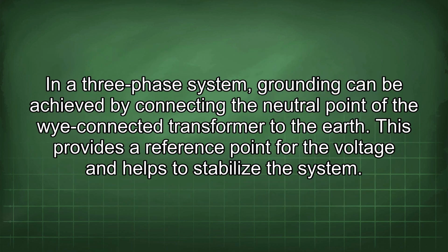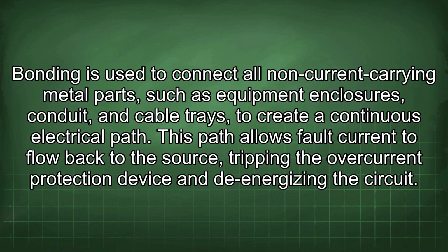In a three-phase system, grounding can be achieved by connecting the neutral point of the Y-connected transformer to the earth. This provides a reference point for the voltage and helps to stabilize the system. Bonding is used to connect all non-current carrying metal parts such as equipment enclosures, conduit, and cable trays to create a continuous electrical path. This path allows fault current to flow back to the source, tripping the overcurrent protection device and de-energizing the circuit.